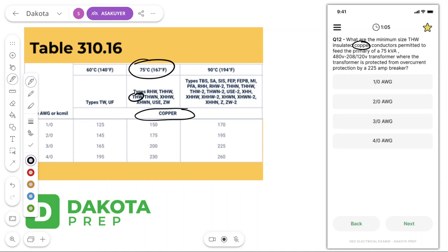Now, we need conductors that can handle 225 amps, right, because that's the size overcurrent protection that we have. And according to, like I said, 240.4, our conductors have to be protected at their ampacity, right? So we need conductors that can handle at least 225 amps. We cruise down our column here. The 3/0 won't quite get it done. Looks like 4/0 is going to be our green ink correct answer.